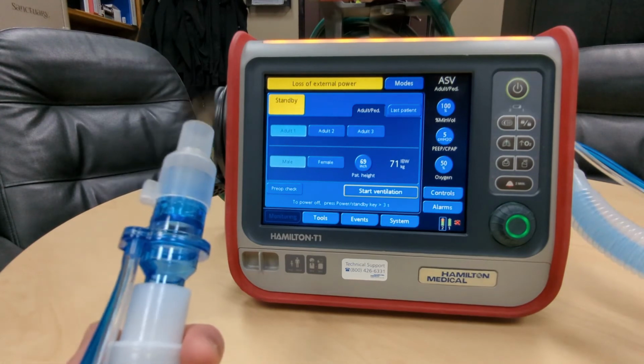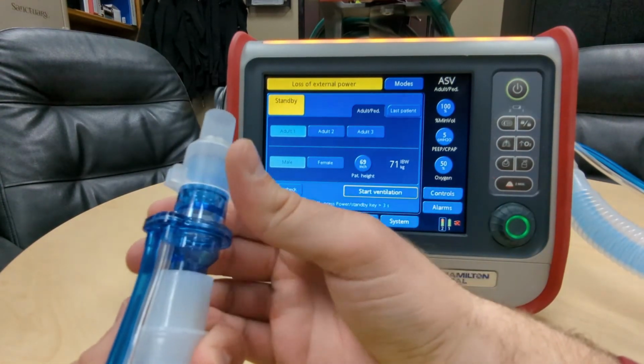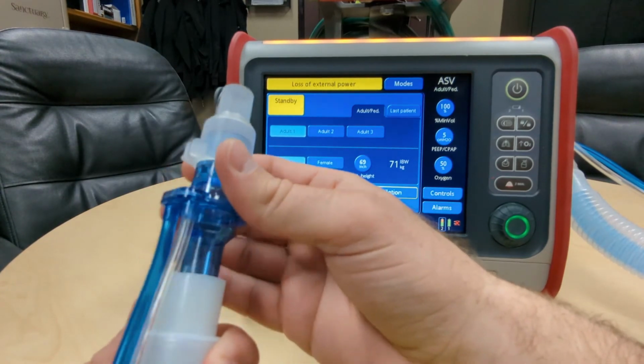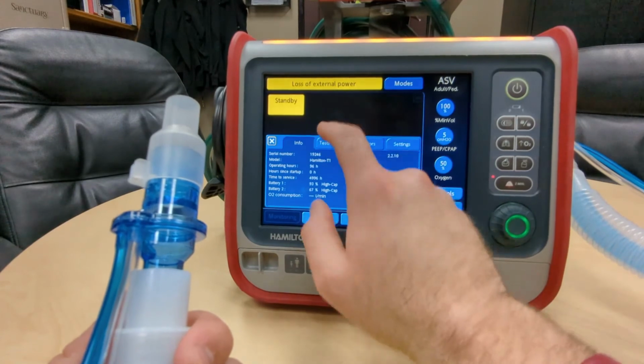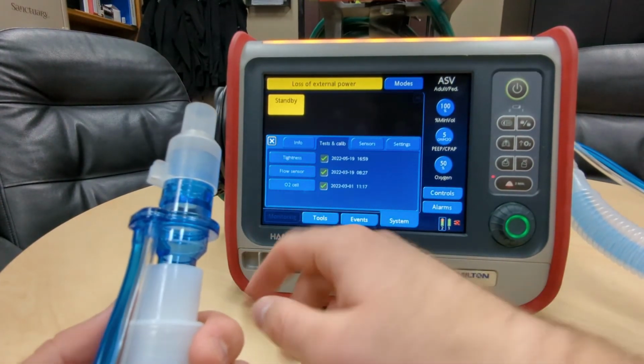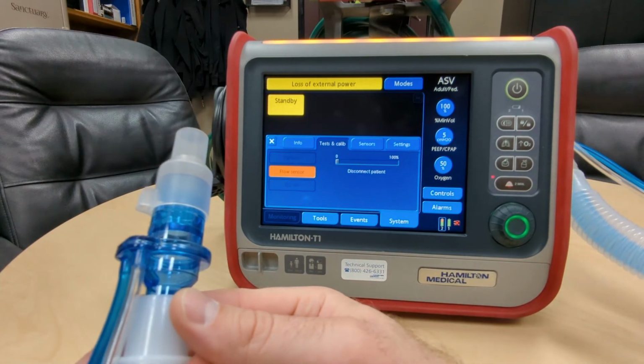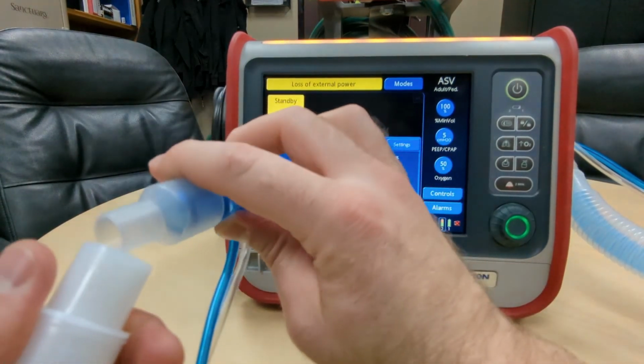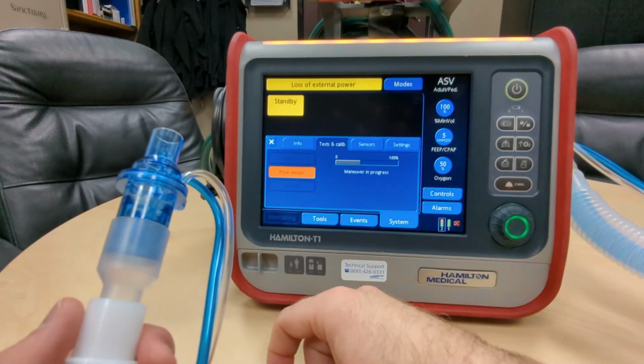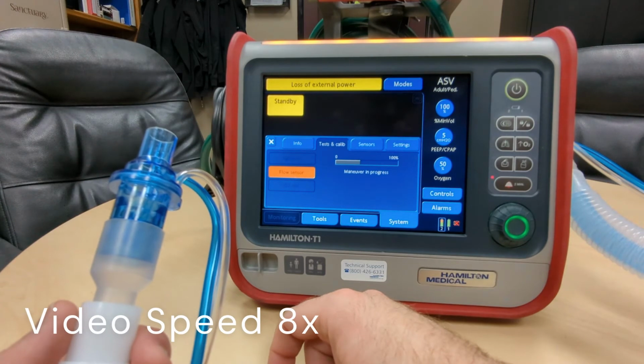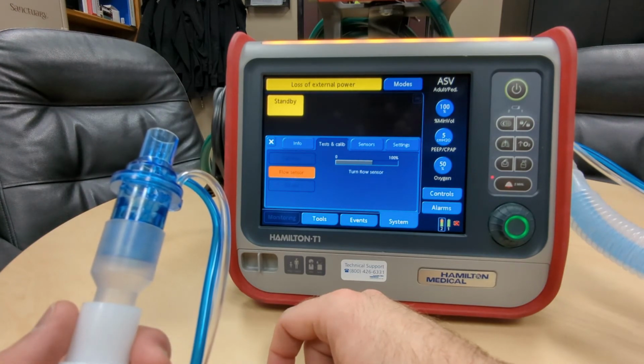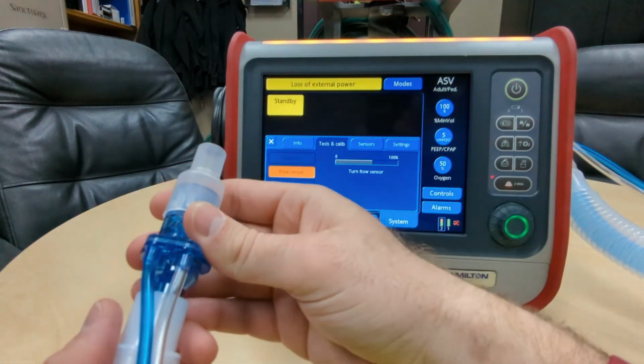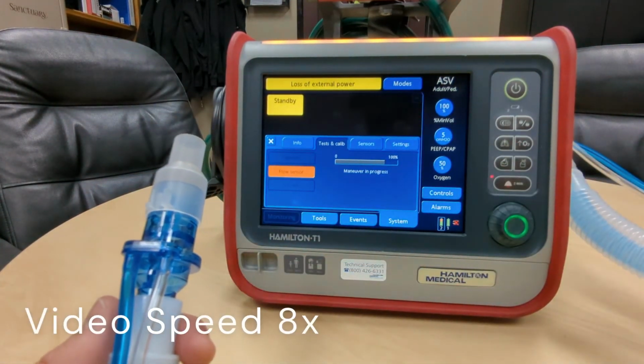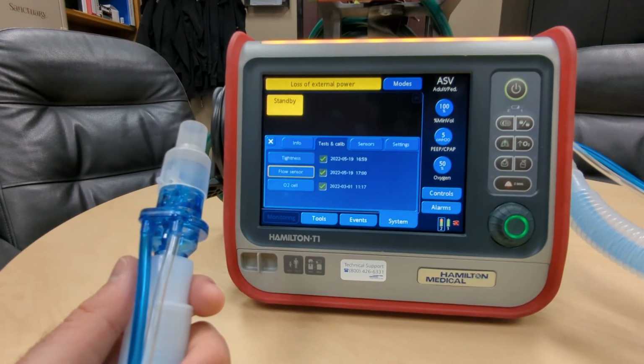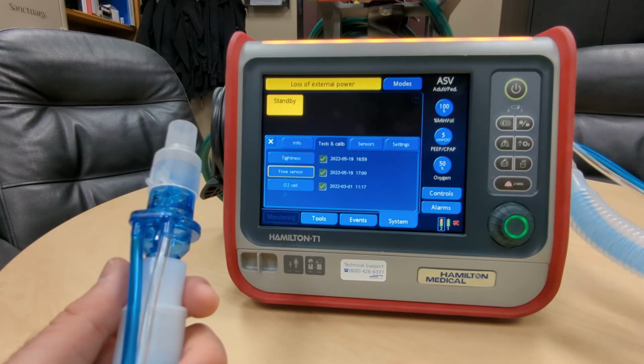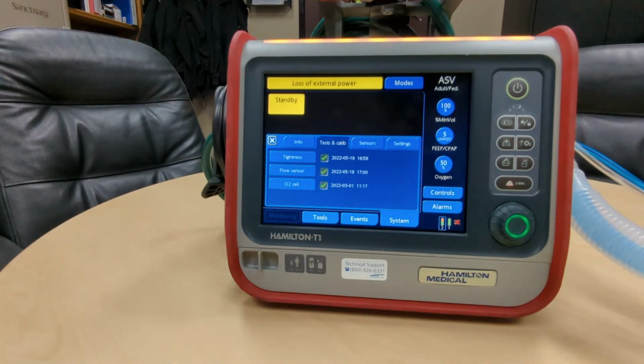For the flow sensor test, I recommend breaking the seal. Oftentimes it's pretty stuck from the manufacturing process. Make sure it's loose. Again, system, test calibrations, flow sensor. When it says turn flow sensor, you only have 4 seconds to make the turn. Turn sensor. Again, make sure there's a green check mark.